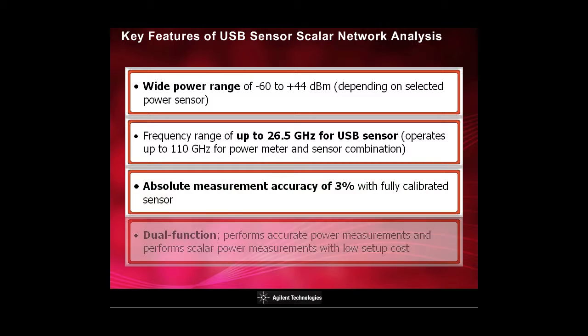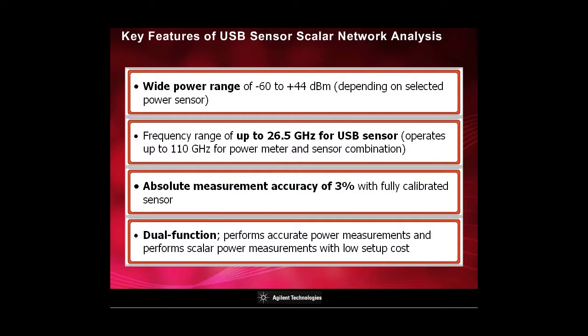The key features of the USB sensor SNA are wide power range, frequency range of up to 26.5 GHz for USB sensor, absolute measurement accuracy of 3%, and dual functionality, which allows accurate and scalar power measurement.